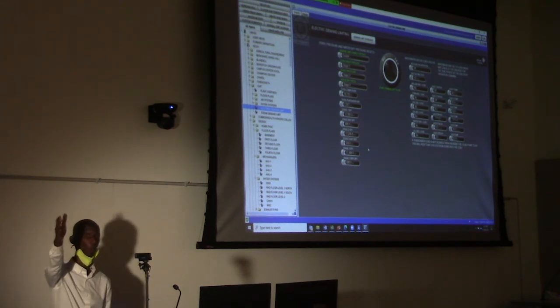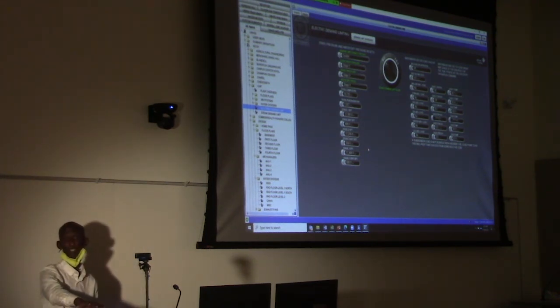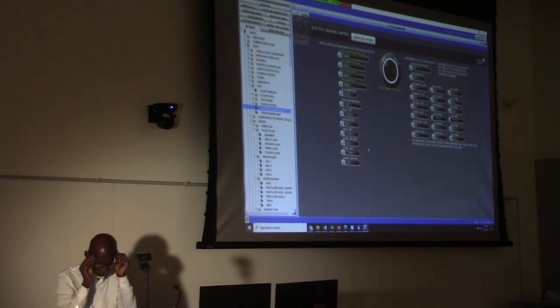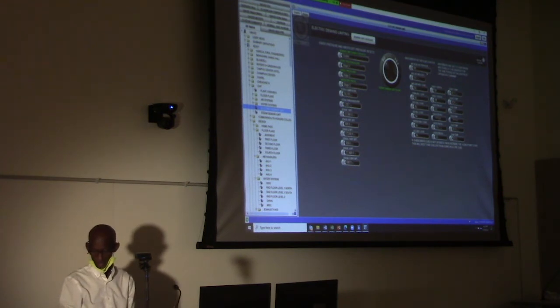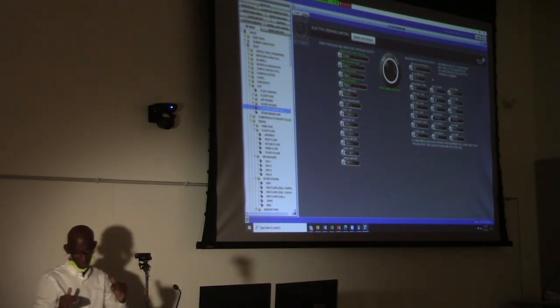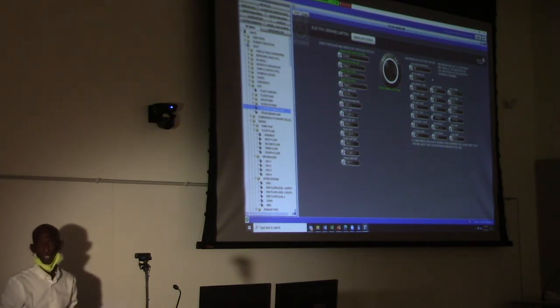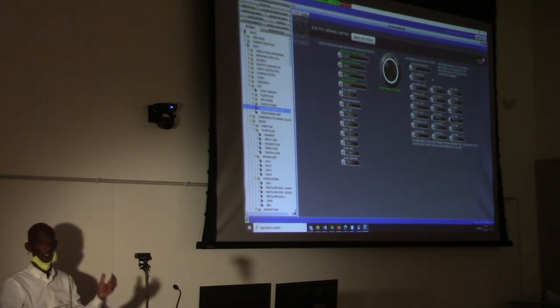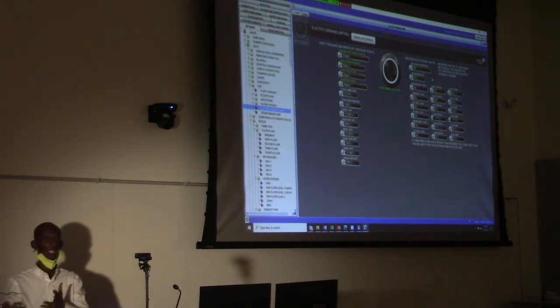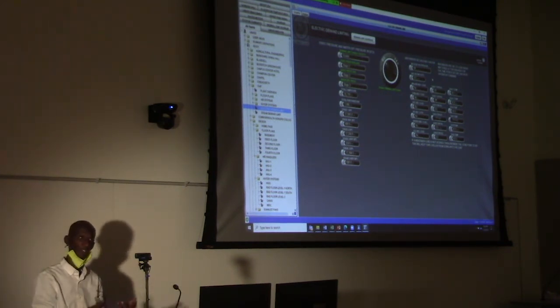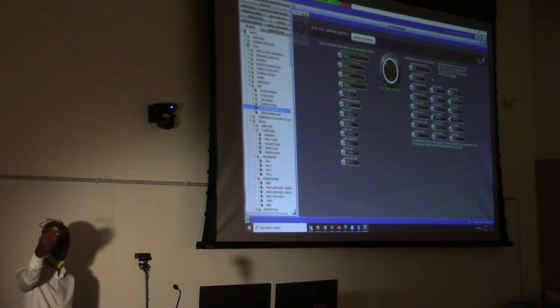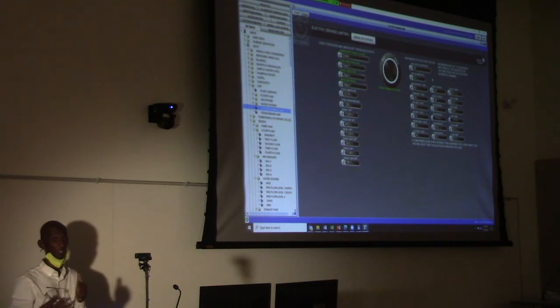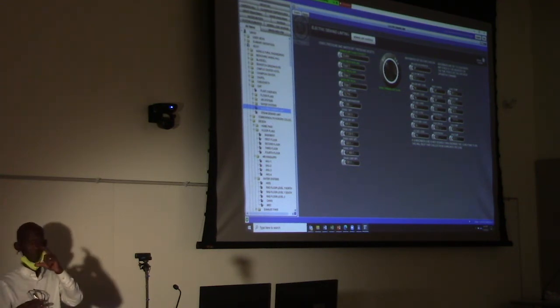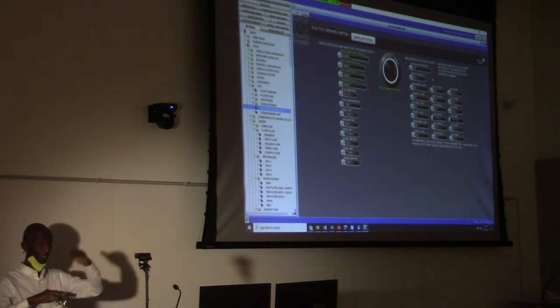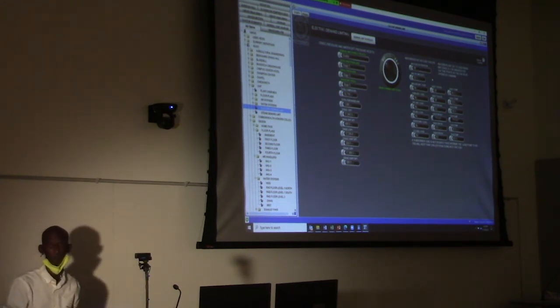Plus, we generate our own power. And if we have control of this, a few times a year, we can generate money for the university. So what we do here, we go into this system, and you can select which chiller we want to run. Sometimes we may run absorption chillers instead of electrical chillers. Electrical chillers use electricity. Absorption chillers use steam. And in the summer, we have the capability of generating steam. So we generate more steam, even though it's a little bit expensive, but for that short period, at least our demand cost is maintained at a lower level.